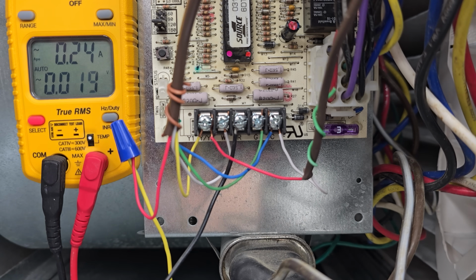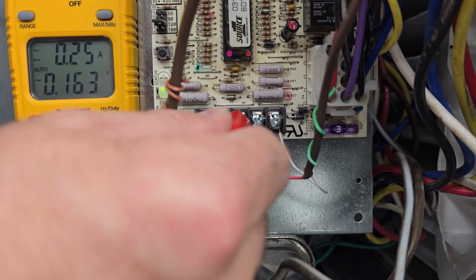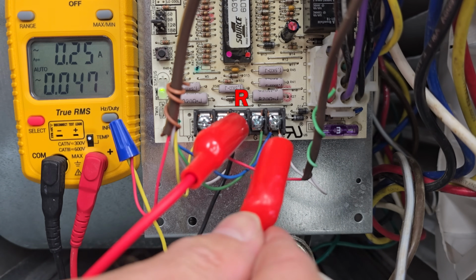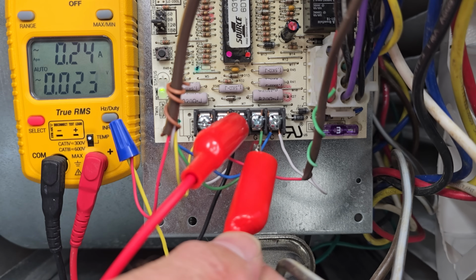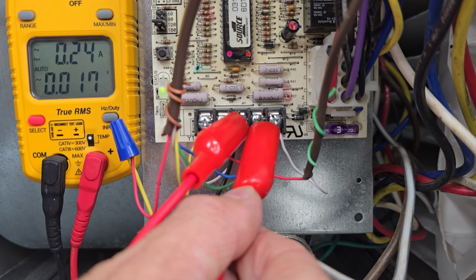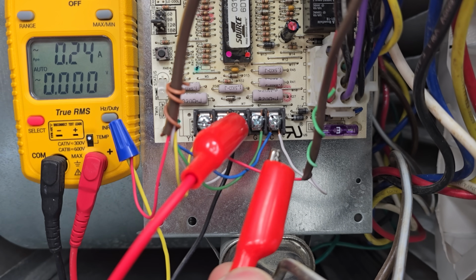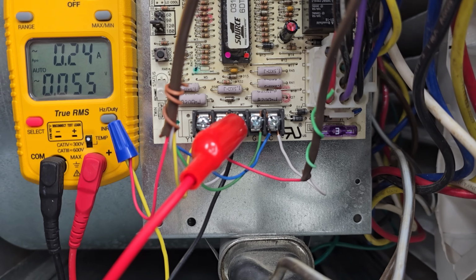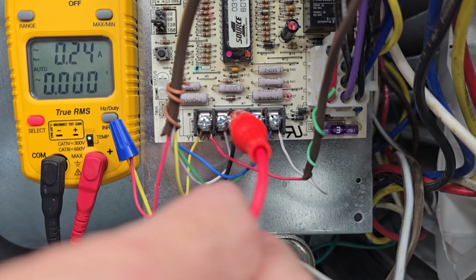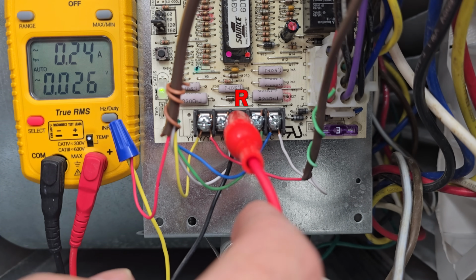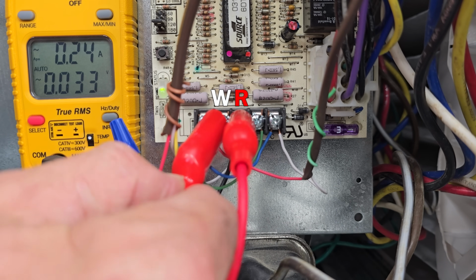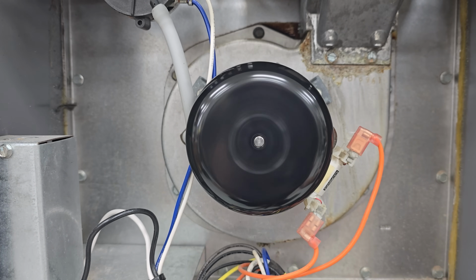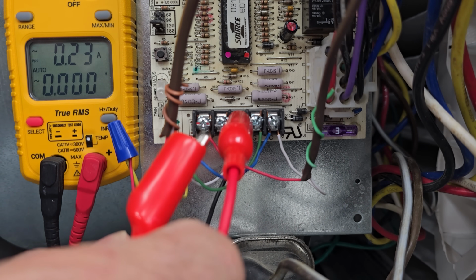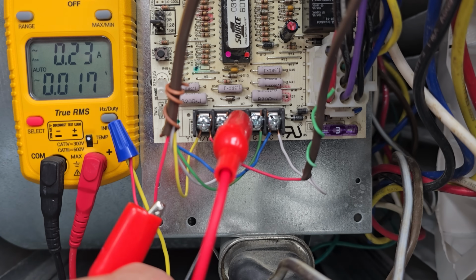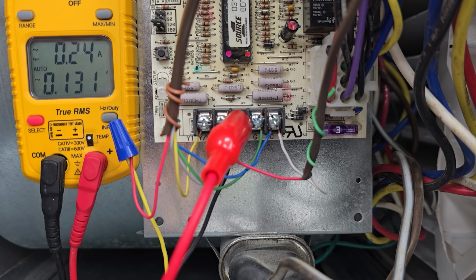I just want to quickly show you that we can get the fan to turn on if we jump from R, which is right here, to G. That's always your indication for your fan to turn on when you have 24-volt power to the G terminal. So we lost our 24-volt power, right? Because we disconnected. Now let's go from our red to W. So that's going to start the inducer motor, which is the sequence of operation for heat. So you can tell our furnace is not having any problems. It's just our thermostat wire to the thermostat itself that has an issue.